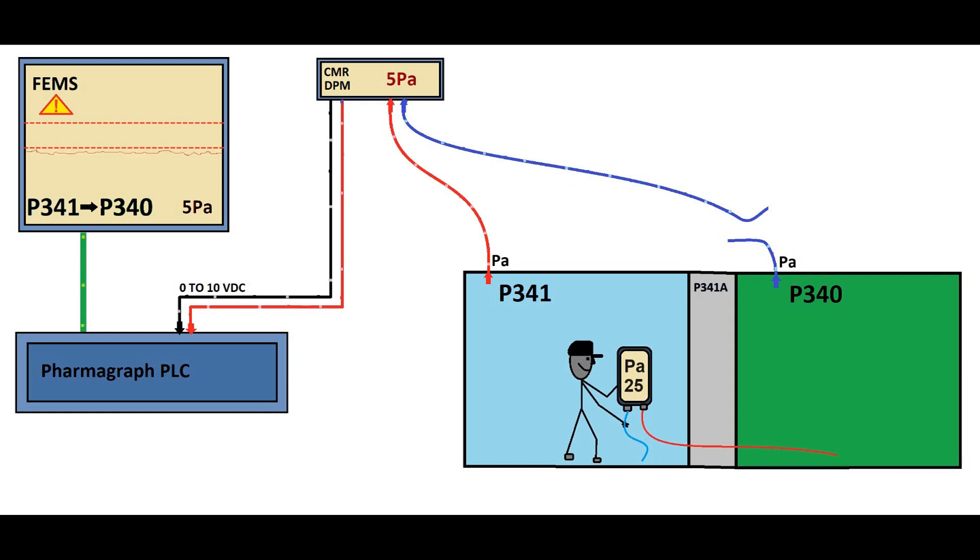A broken tube in the link between the differential pressure module and the affected rooms is identified during this investigation. This revelation is crucial insight for the root cause of the anomaly, reinforcing the necessity for remedial action.